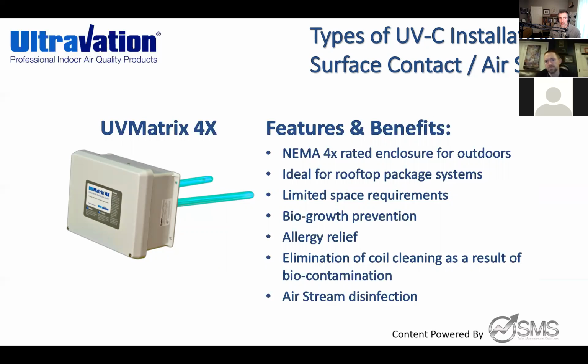But with the UV Matrix, this is popular because it's a NEMA 4X rated enclosure - that's why it's called the 4X version of the series. It's all waterproof, completely sealed. The big win here is that we can put these UV bulbs into a space in front of a coil or right at an access point to supply air from the coil. You're not putting all that electronic hardware inside the HVAC equipment - everything is externally outside of the equipment, as you can see here with the power box. Then you're just cutting access holes to get the UV bulbs into that area.